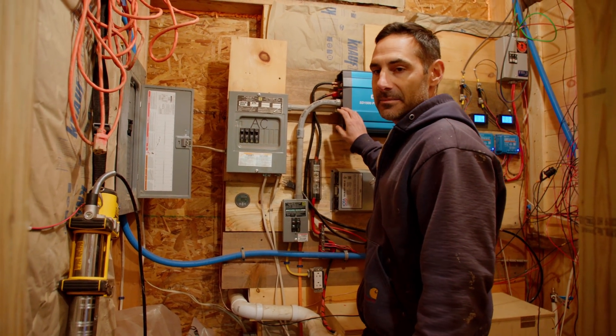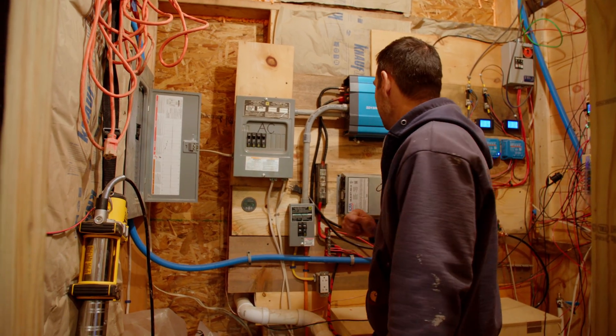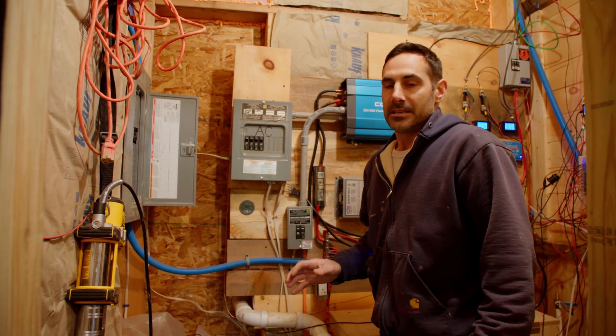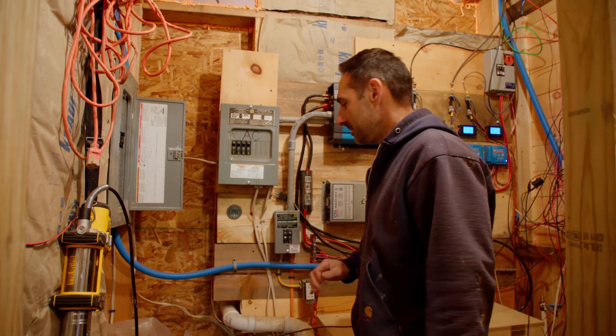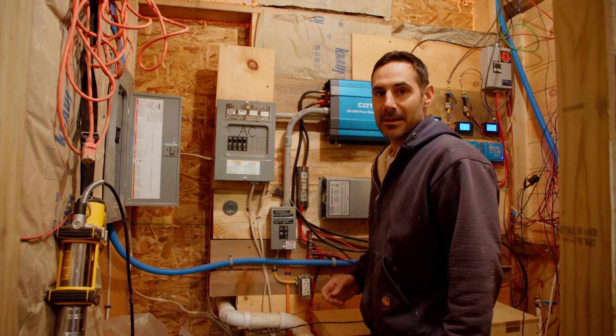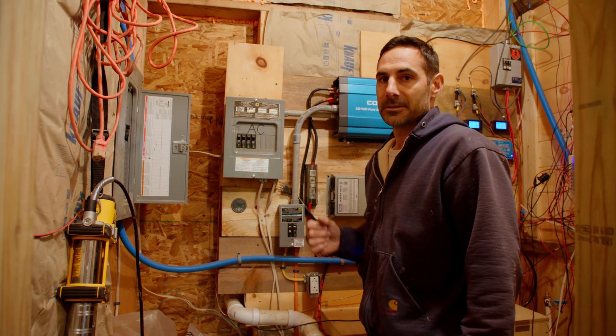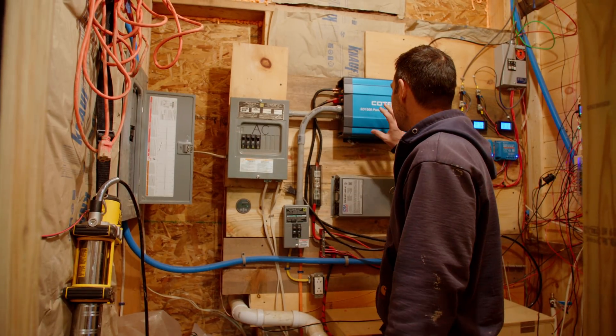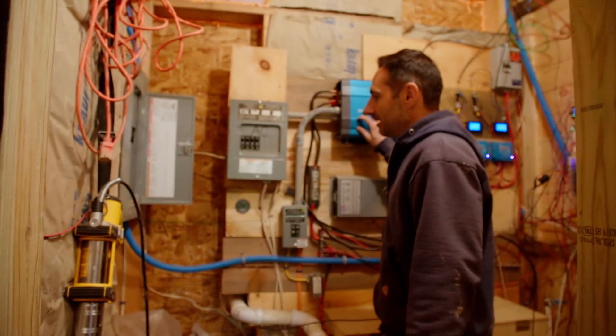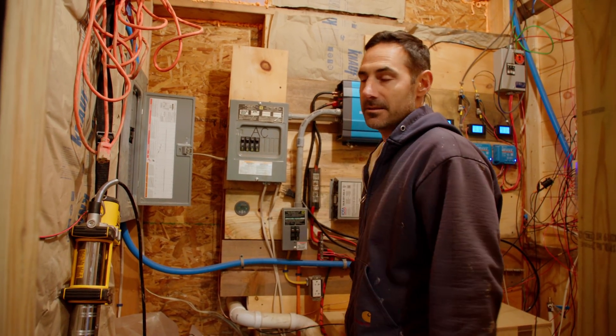For me, I don't really need to do that because I don't use my inverter for anything much except when I need to plug something in. I've wired this whole cabin for DC, so the inverter is not a major component that's going to lead to a low voltage situation. But if you run everything off your inverter, you should definitely have an inverter that can program a low voltage disconnect of — I think it's 25.2 or 25.1 volts if you want to go like 80 or 90% discharged.